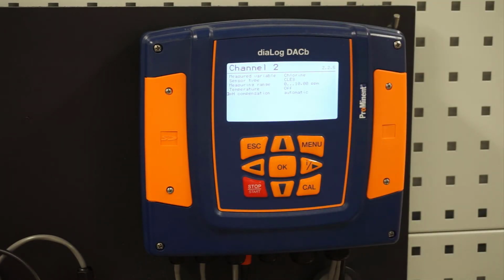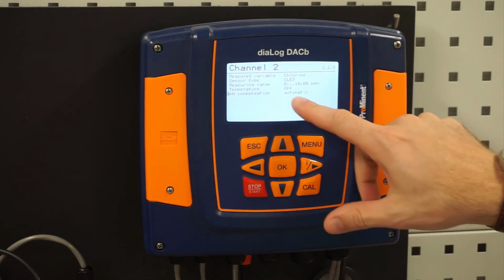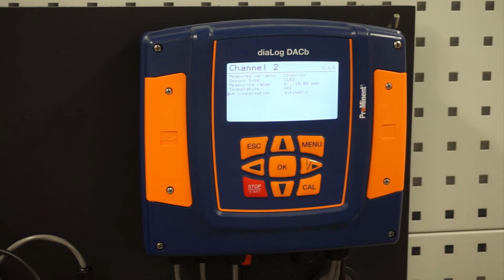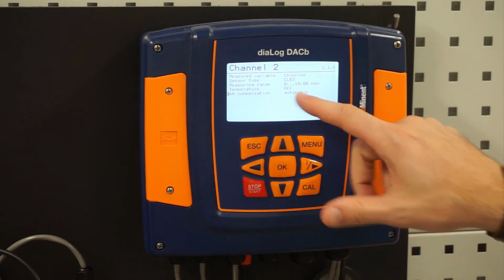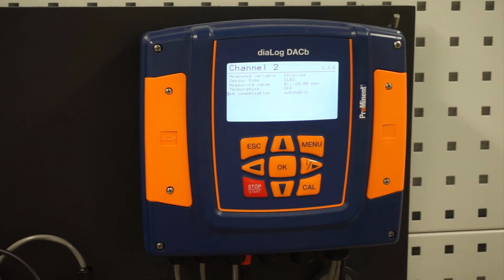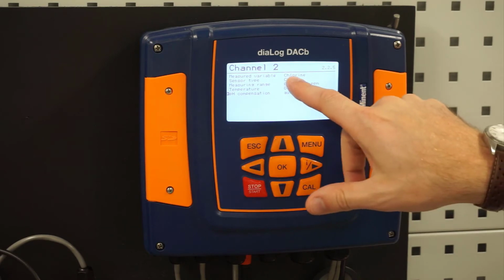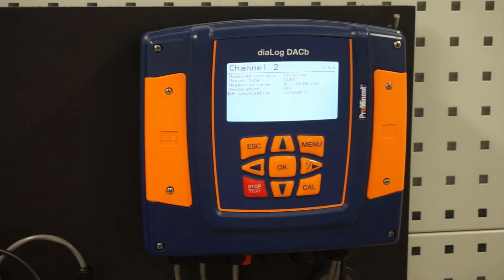An important note is if you change anything in this screen after you've done all your other programming for your control outputs, it's going to wipe out whatever I have set up for my control outputs. And that makes sense. If we're changing something in here, we should probably go and look back at our control outputs to make sure it matches up. Especially if we're changing sensors from maybe chlorine to PAA, we're most likely not going to keep the same control parameters. So once we make those changes, it will wipe that out. So be aware of that.